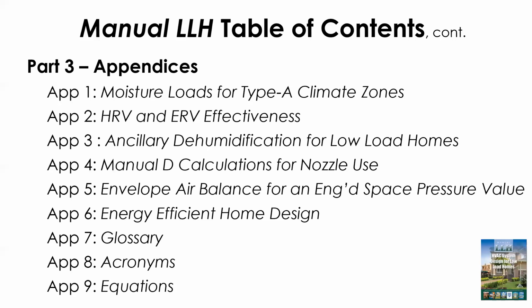And of course, one of the big ones is Manual D calculations for using nozzles. The reason for that is because of the low airflows, the typical 10 by 4s and 10 by 6 ceiling diffusers that we're used to using do not function well down at the 50 and less CFMs. So you're going to have to use something different if you're going to use conventional equipment. Basically, manufacturers are now offering nozzles to be used with split system air conditioning, other than just small duct high velocity systems. Then it talks a little bit more about energy efficient home design and how Manual LLH applies to some of that.